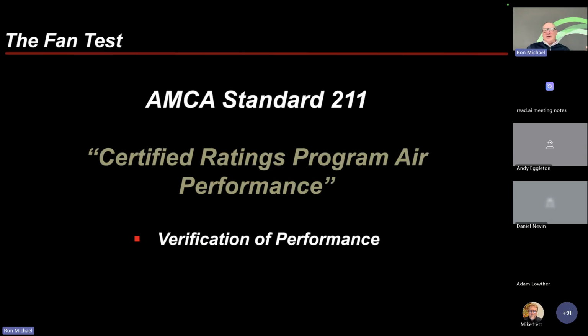Okay. Then what we do is we'll send all that data to AMCA, and they'll certify the data. So they'll actually take test data from, let's say, the Cook lab. They'll select random fans. We'll send them to Chicago to the AMCA lab, and they'll test them in both labs, and the data has to fall within a very tight percentage to actually receive a certification. So really all the manufacturers' data is certified on the same lab in Chicago.